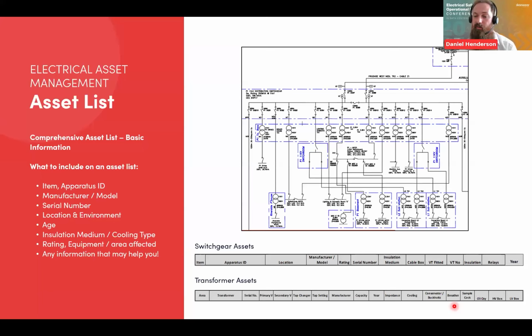From an oil sample perspective - does it have a sample point? A lot of transformers, not just old ones but new ones, if it's not specified, will come without a sample cock fitted, which hinders us from a maintenance perspective because you can gain so much information from oil analysis on your assets.